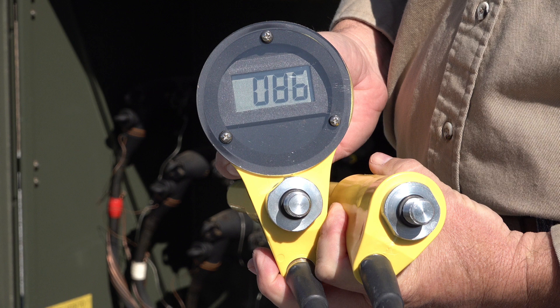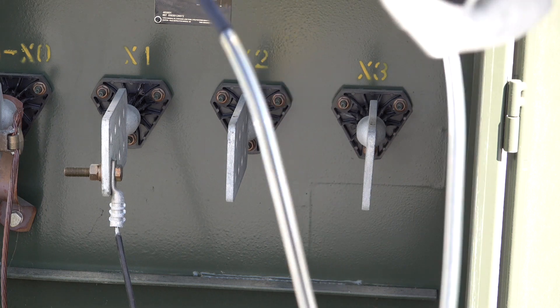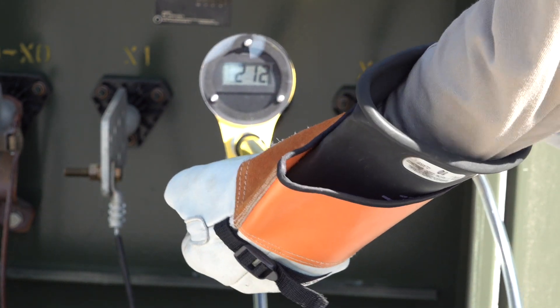This meter has 0.86 volts. The next test is what's considered a known voltage test. Since we know this three-phase pad mount is energized and we touch the X2 and X3 bushing, we should get close to 208 volts.